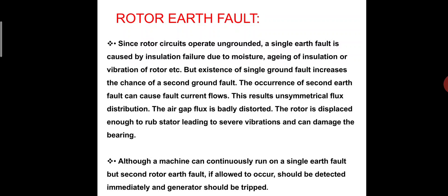This results in unsymmetrical flux distribution. The air gap flux is badly disturbed. The rotor is displaced enough to rub the stator, leading to severe vibrations, and can damage the bearings.